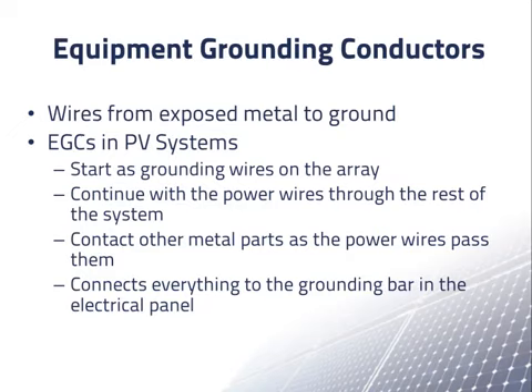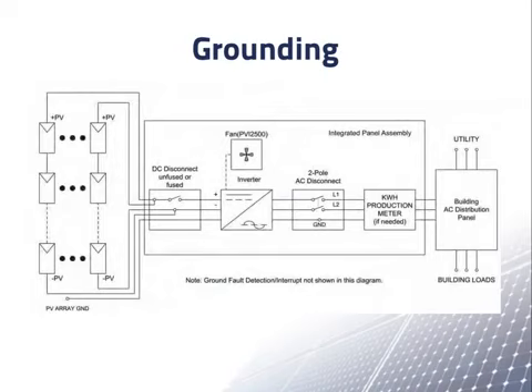In this diagram, an equipment grounding conductor begins by connecting to all exposed metal parts in an array. The equipment grounding conductor may have several branches within the array. The conductor continues with the power wires through the DC disconnect to the inverter, where it is connected to another equipment grounding conductor which goes with the AC wires through various parts to the grounding junction in the electrical panel.